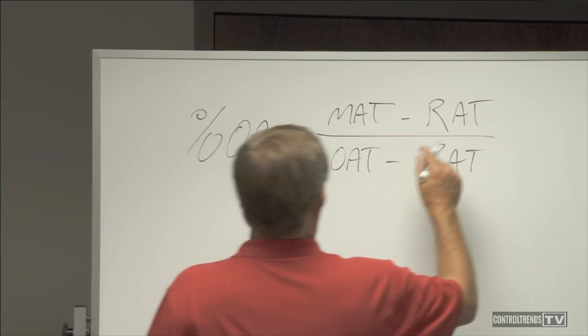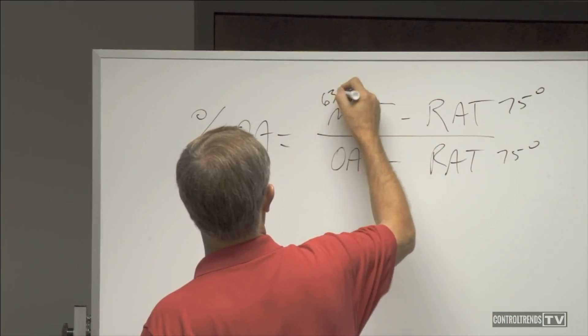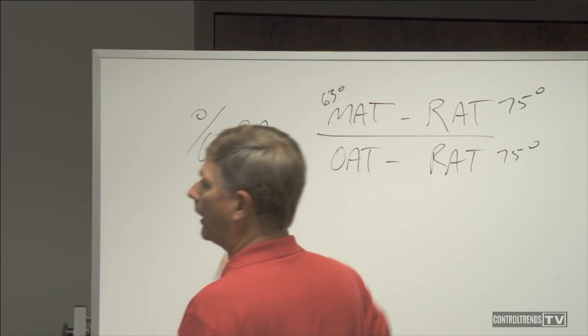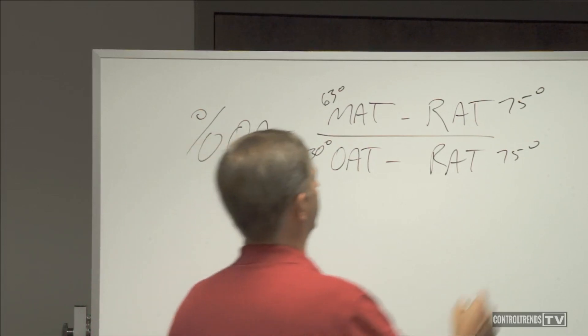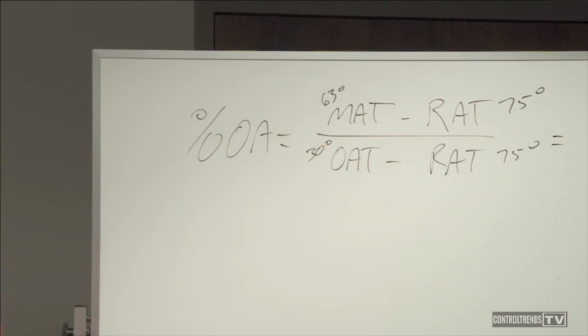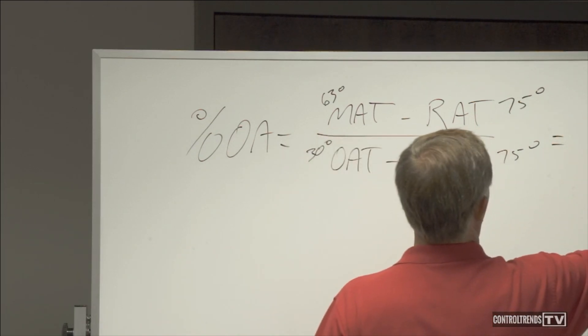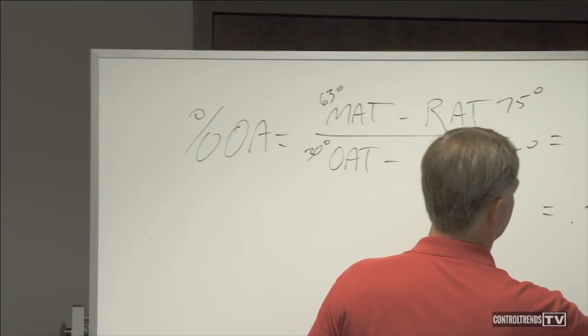If we said our return air is 75 degrees, mixed air, this is saying it's 63 degrees. Outside air, they were saying it is 30 degrees. So, what do we have here? This is advanced math, isn't it? Somebody want to work the math for me? We have all these smartphones in this room. What's the difference between 63 and 75? What's the difference between 30 and 75? All right. 12 divided by 45 equals?